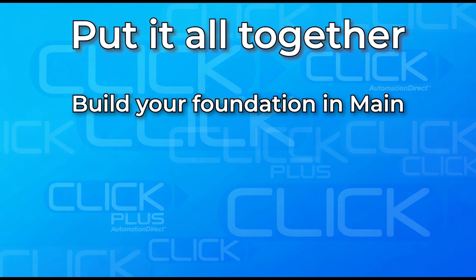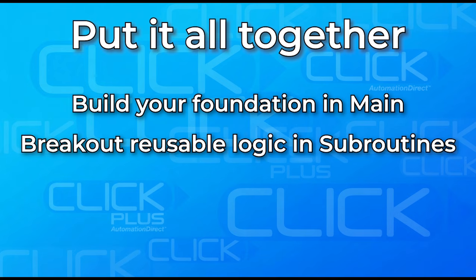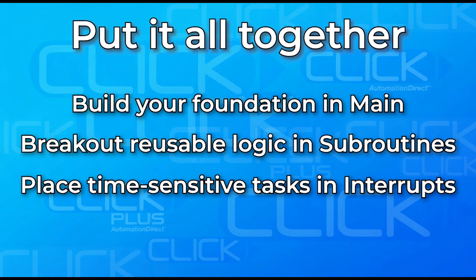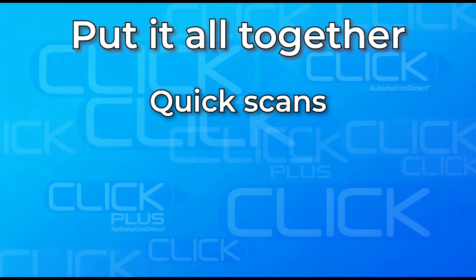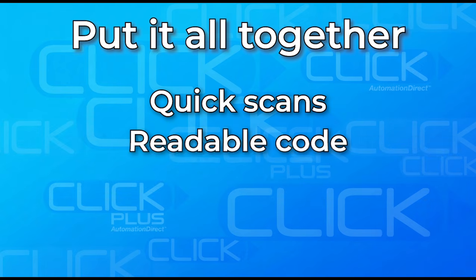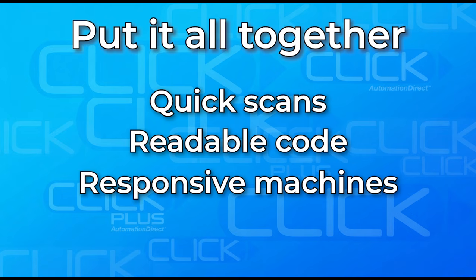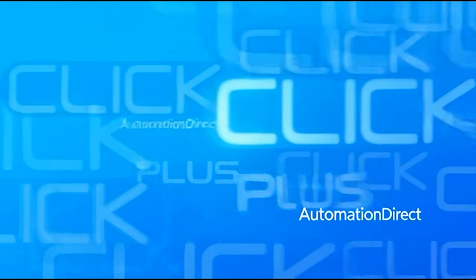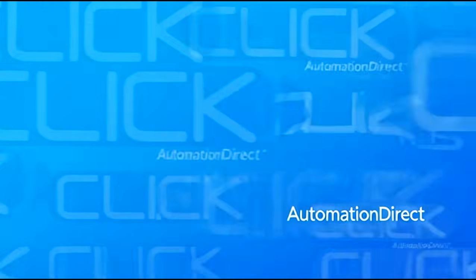Put it all together like this. Build your foundation in the main program, break out reusable or conditional logic into subroutines, and protect time-sensitive tasks with interrupts. That separation keeps scans quick, code readable, and your machine responsive. Open the free CLICK software, experiment with these program types, and check the built-in help.